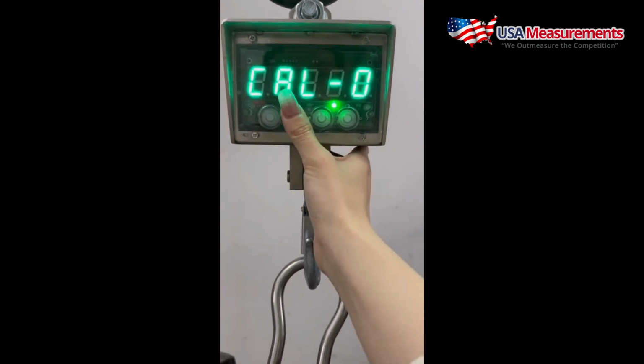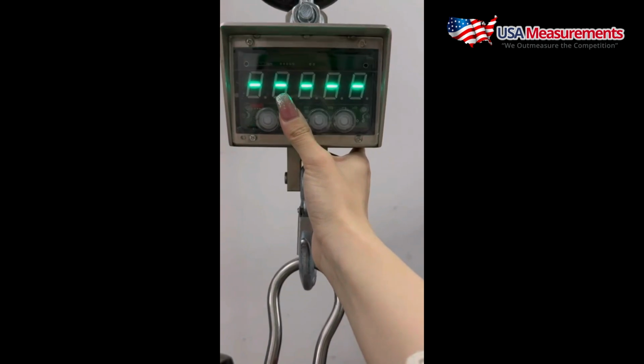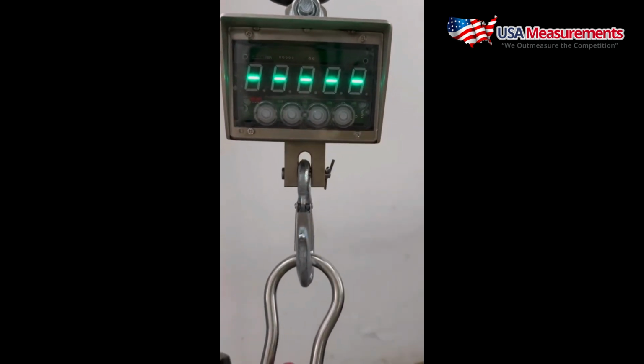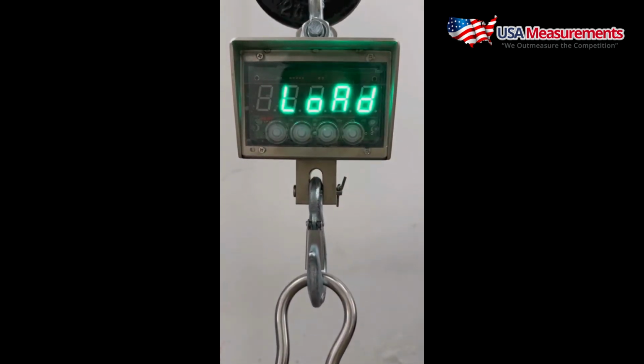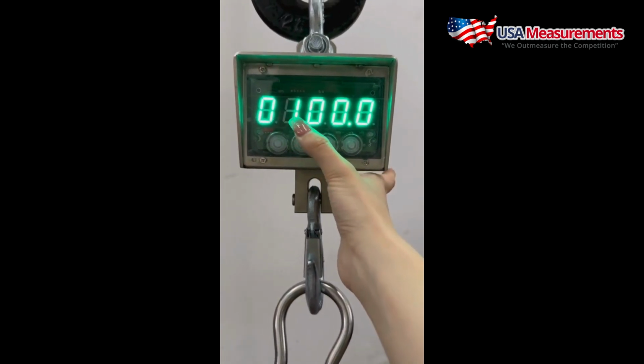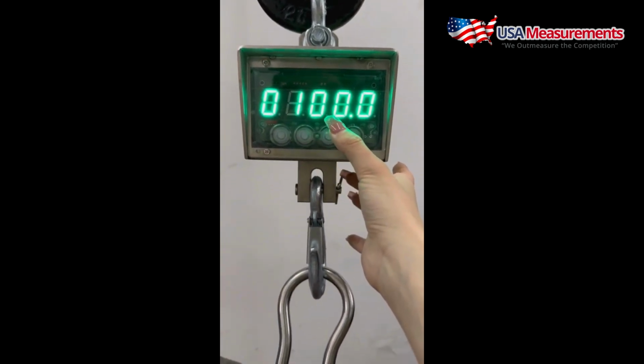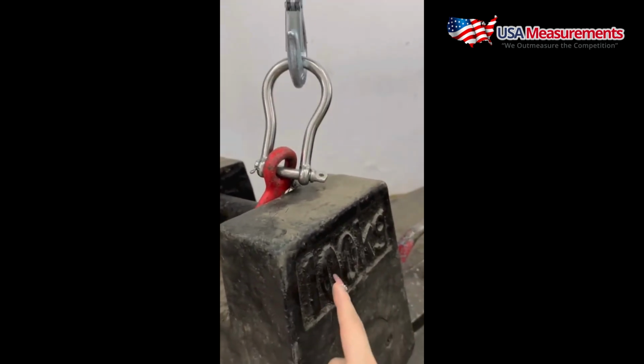Now we'll capture the 0 point. With nothing hanging on the scale, set the 0 point. Next, enter the value of your calibration weight. Ours is 100 kilograms. Enter 100 kilograms as your standard weight.